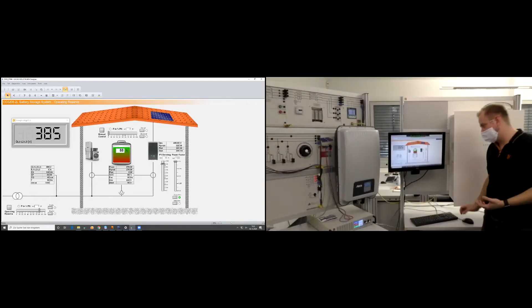And this is part of the grid code in Germany or in Europe? In Europe, yes, it can be. It depends on the power of the PV system. So if you reach a certain power and you don't have other devices that limit the grid feeding, they can say you have to derate it. Also, it's possible, like we are doing, over a communication interface, to do it not statically but dynamically, depending on the voltage of the grid.